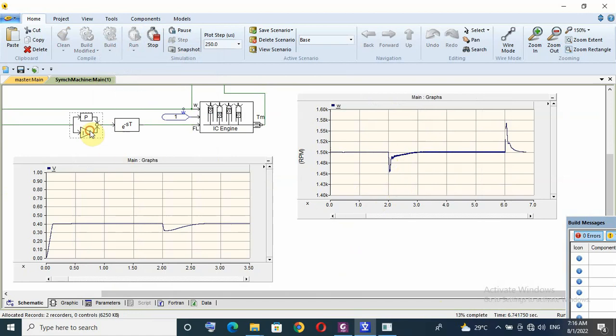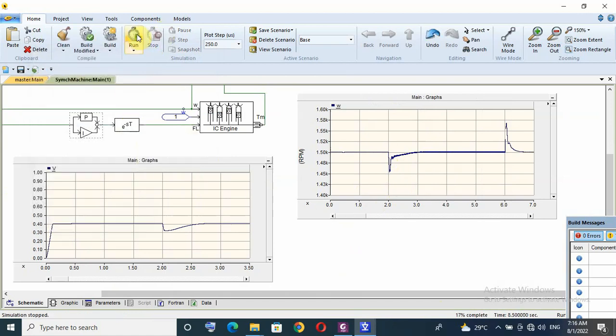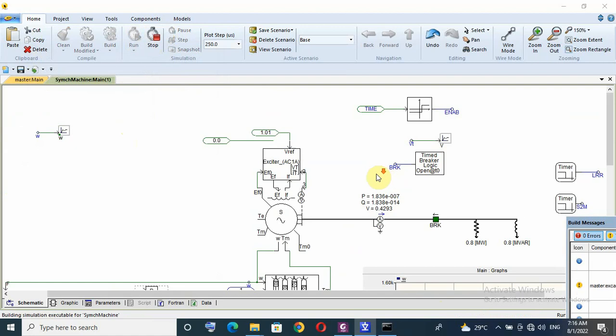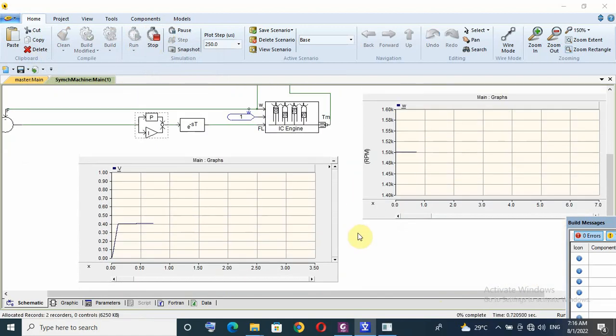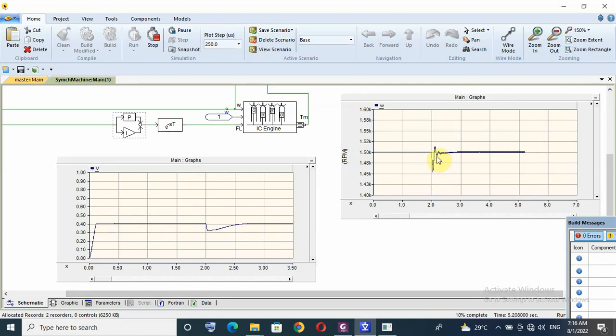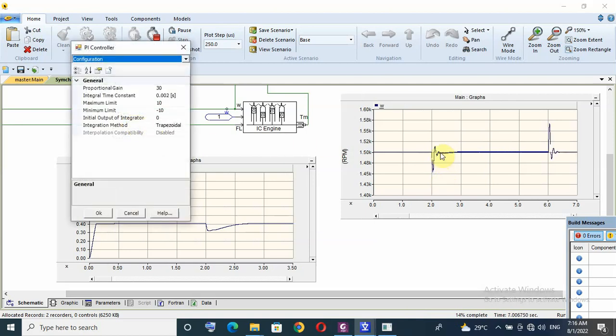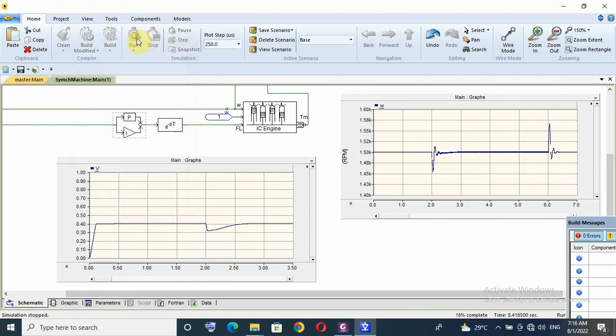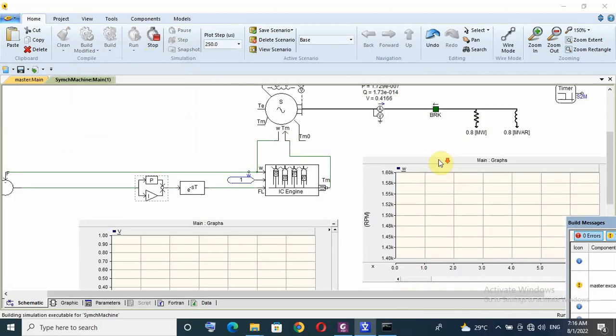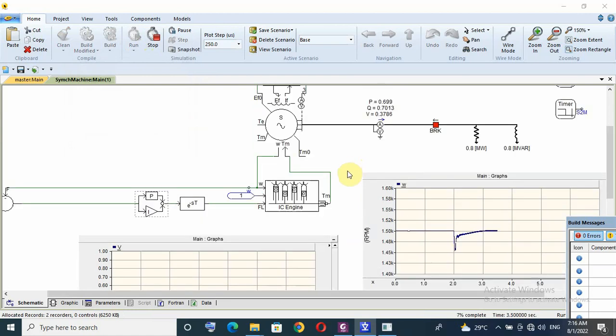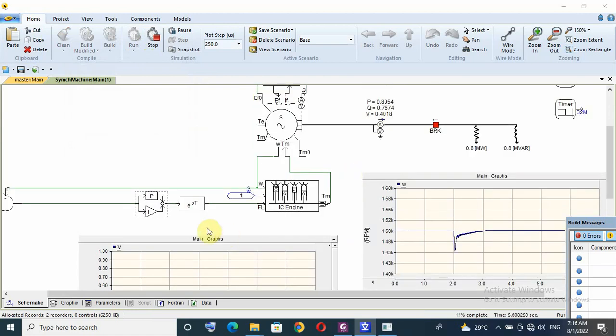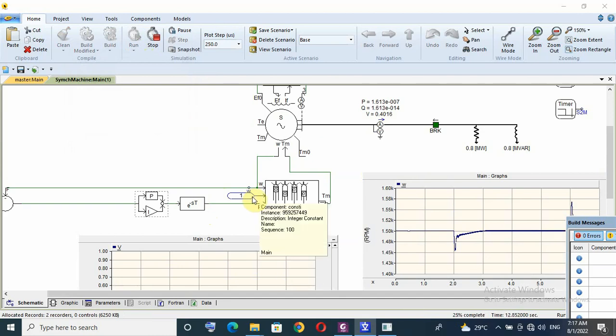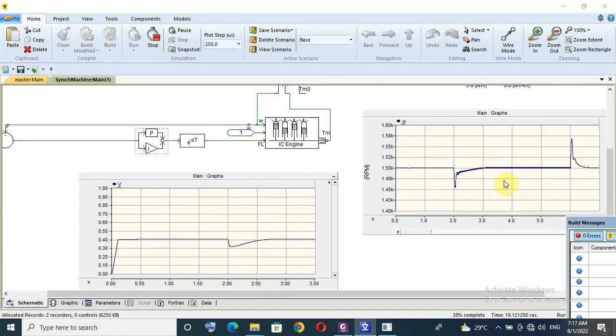If we increase the integral time... no I think now here because this is more so I have 0.05 is okay. In practical how I can tune this speed controller: I have to increase the proportional gain up to I get oscillation, then I decrease the proportional gain and I do the same thing for integral gain.